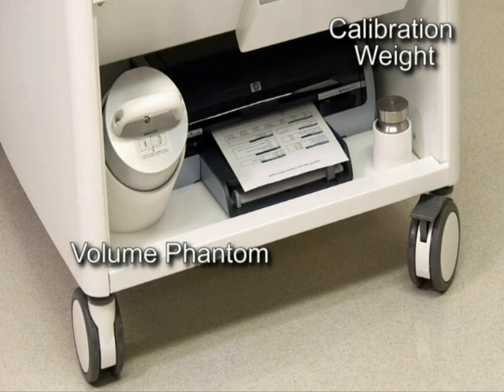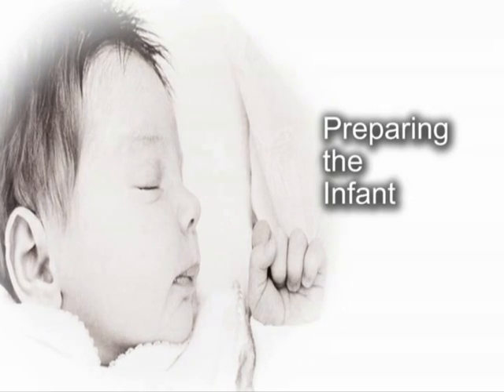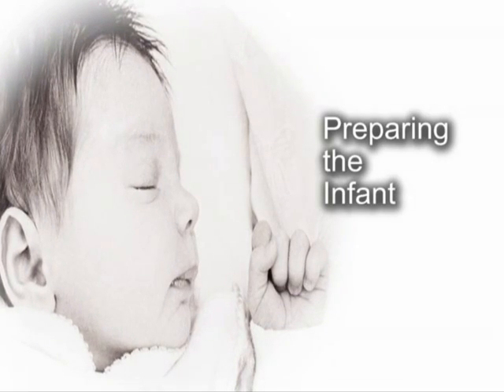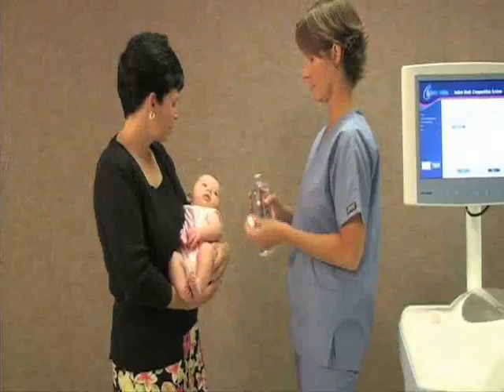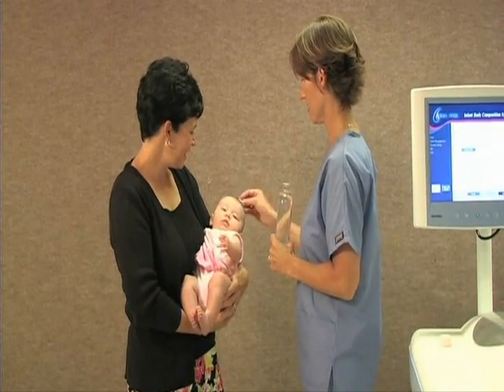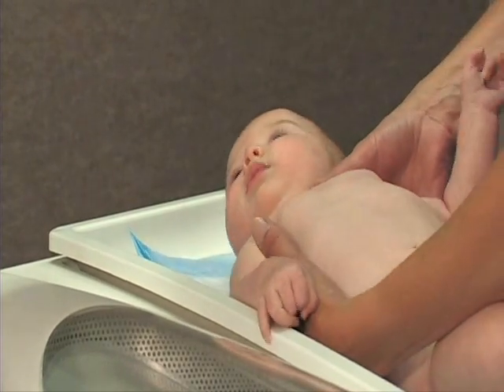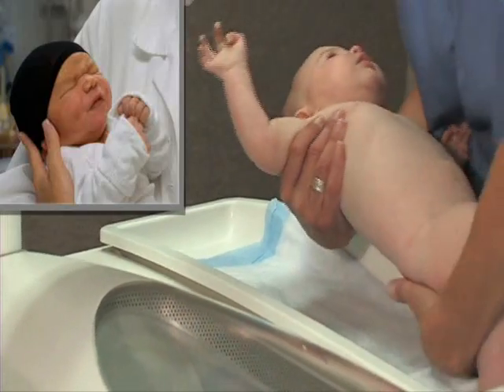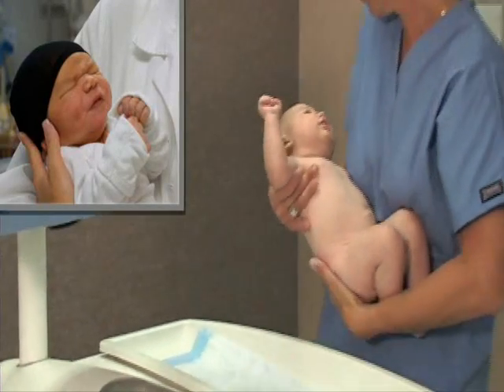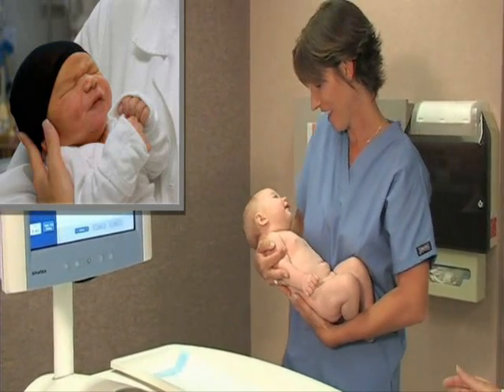Calibration standards are also included for evaluating the PEA POD's performance. An entire PEA POD test, from start to finish, takes approximately five minutes. To ensure accurate results, it is very important that infants are tested nude and that they have their hair flattened with baby oil prior to beginning the test. Infants with curly or large amounts of hair should wear a cap provided by LIFE Measurement during the body composition test to compress their hair.